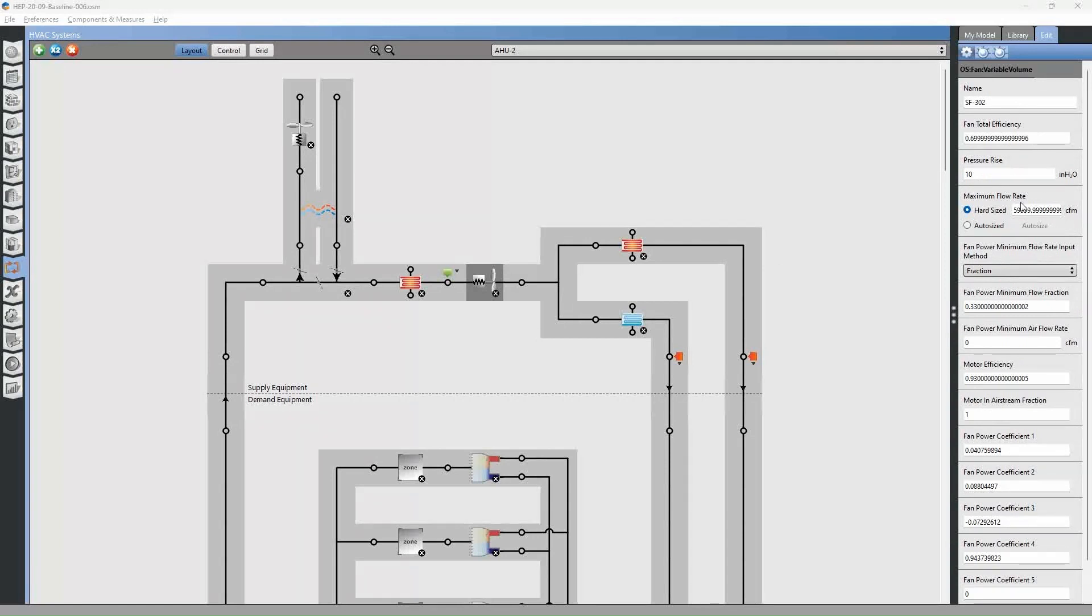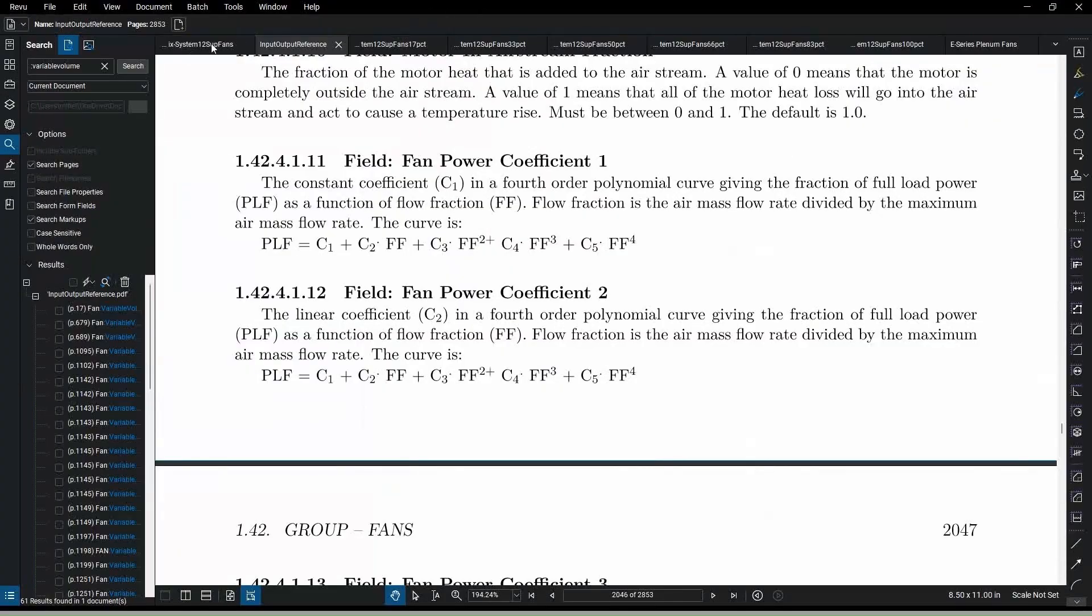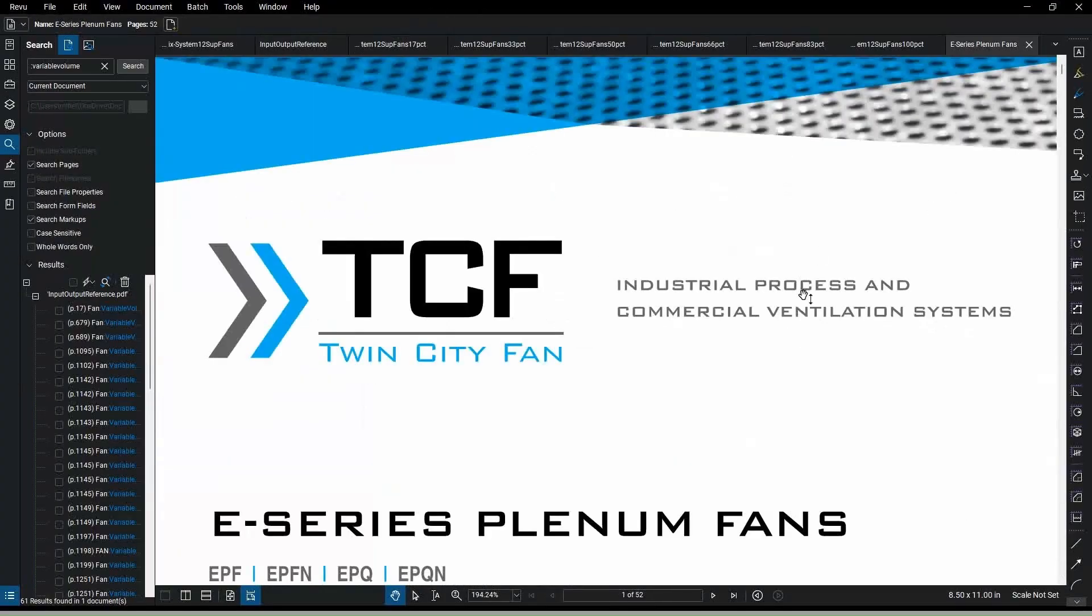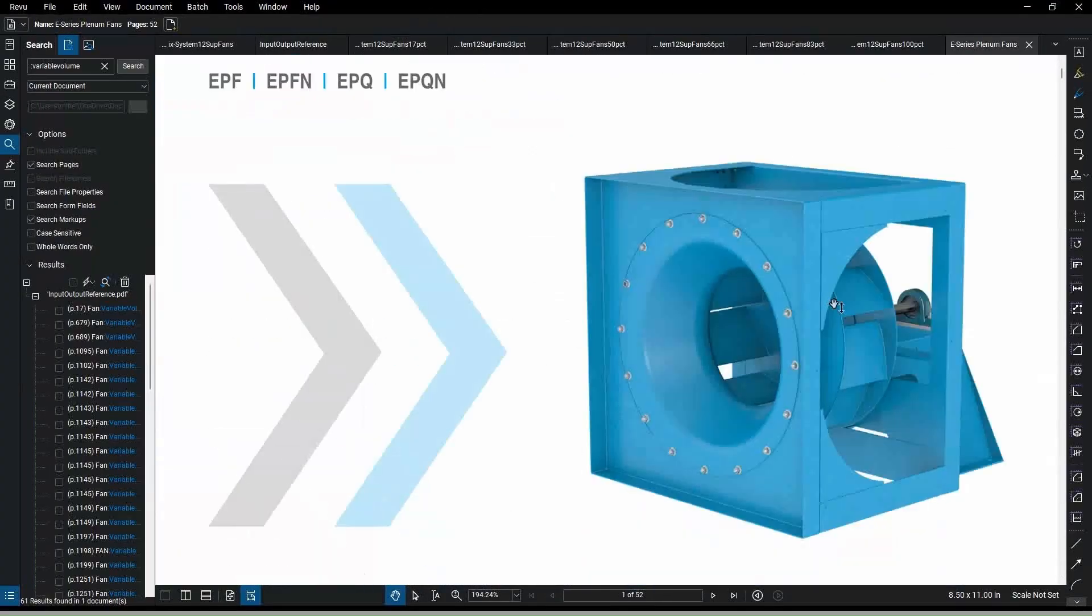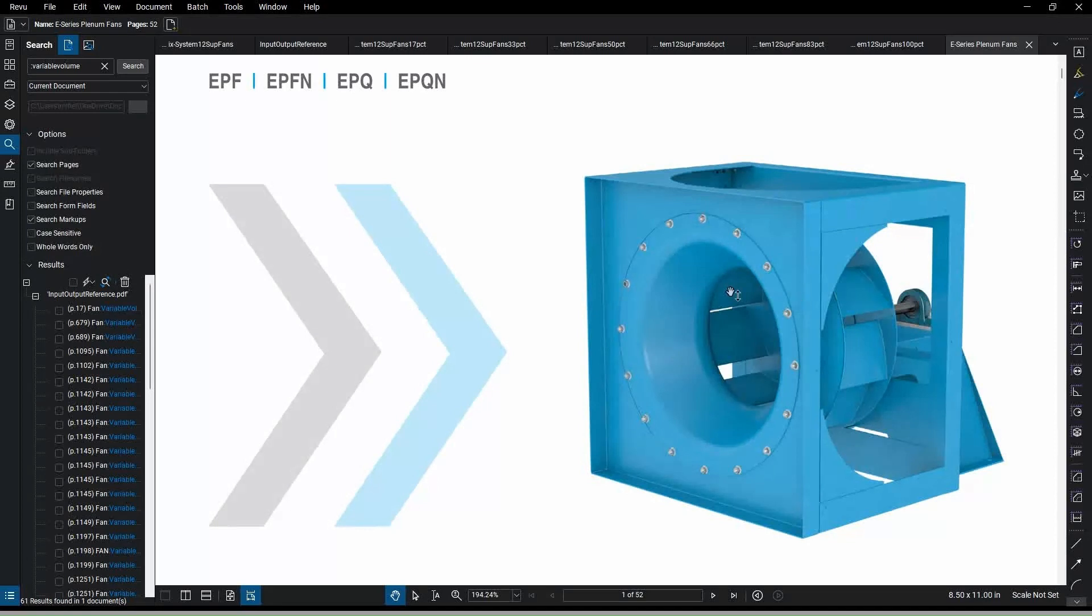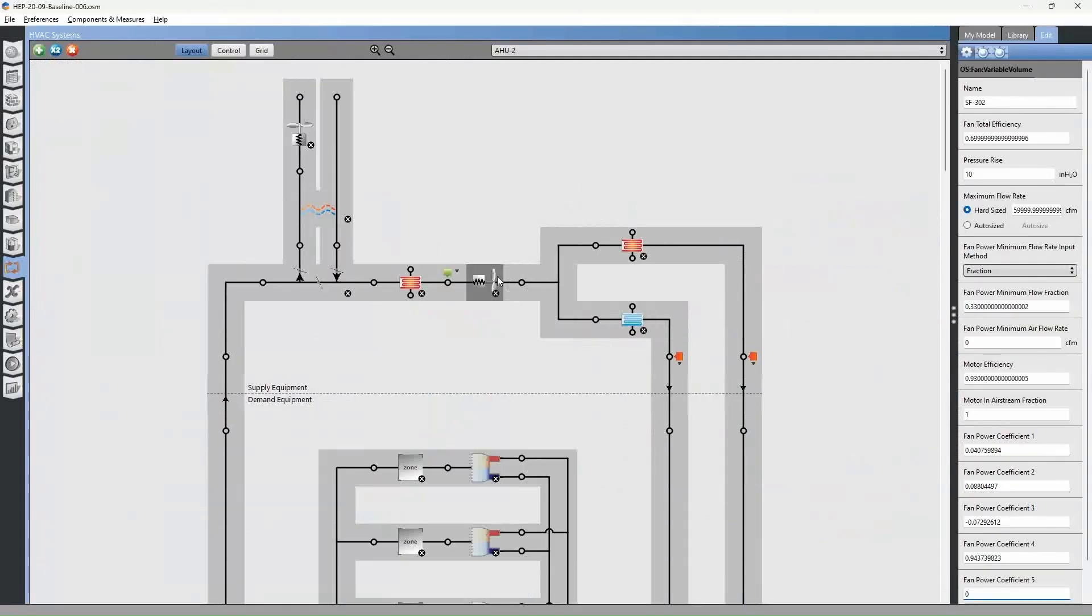The fan curves that they use are a pretty good general-purpose curve for a fan, but what if we are doing something like multiple fans, multiple plug fans in parallel, for instance? Well, in order to do that you have to create a custom fan curve that is specific to that array.